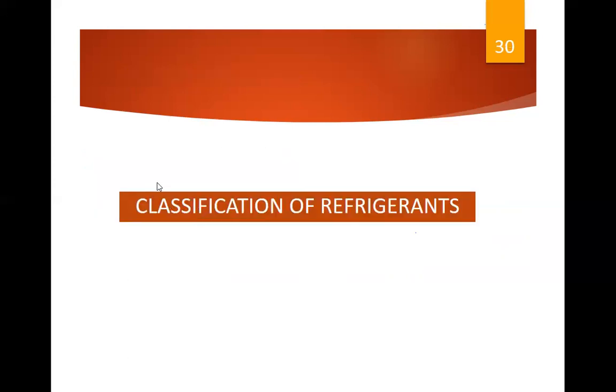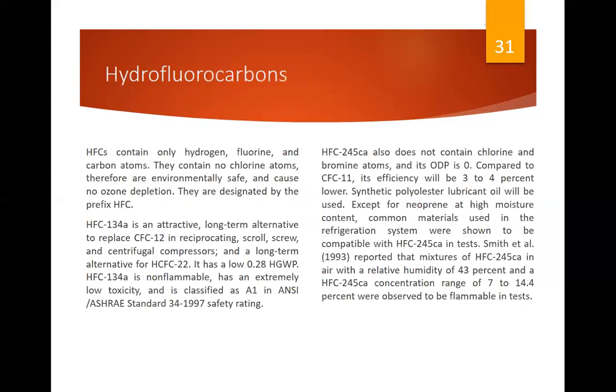Next, classification of refrigerants. Hydrofluorocarbons. HFCs contain only hydrogen, fluorine, and carbon atom. They contain no chlorine atom, therefore are environmentally safe, cause no ozone depletion. They are designated by the prefix HFC. HFC 134A is an attractive long-term alternative to replace CFC 12 in reciprocating, screw, and centrifugal compressor, and a long-term alternative for HCFC 22. It has a low 0.28 HGWP. HFC 134A is non-flammable, has an extremely low toxicity, and is classified as A1 in ANSI ASHRAE standard 34/1997 safety rating.